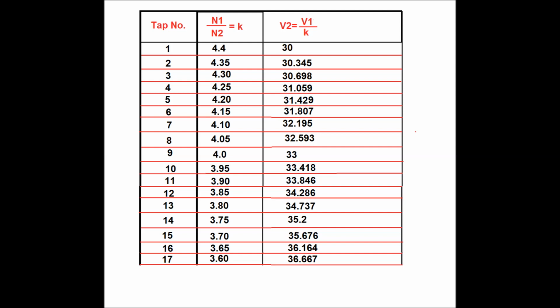At tap position 17, that is, the minimum of the HV side winding is selected, so the maximum voltage at the LV side can be obtained.